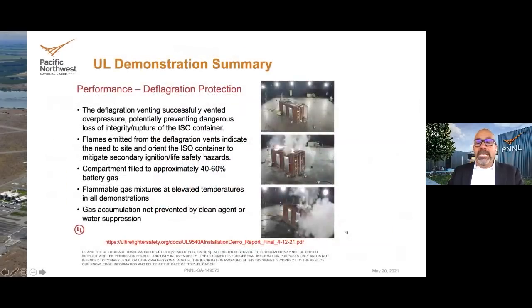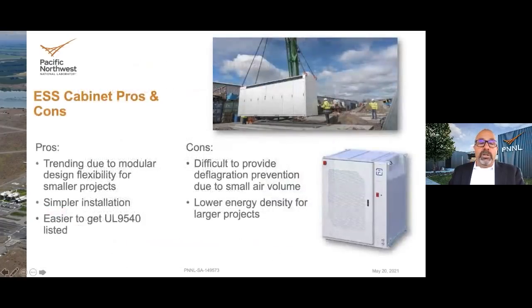In each of the tests, what they were able to prove was that the deflagration venting successfully vented the overpressure, and flames were emitted from those vents, but each of the compartments filled to approximately 40 to 60% of battery gas at elevated temperatures. The gas accumulation was not prevented by clean agent or water suppression. That really highlights the gap that we wanted to address with our solution.